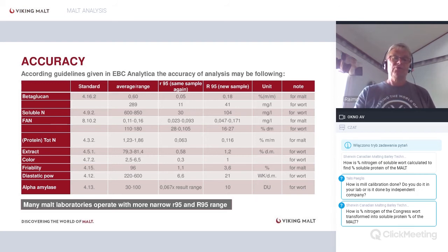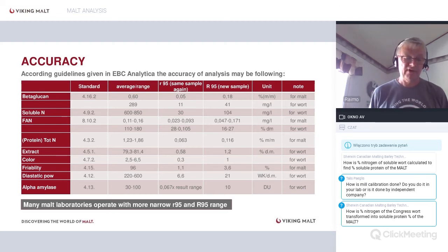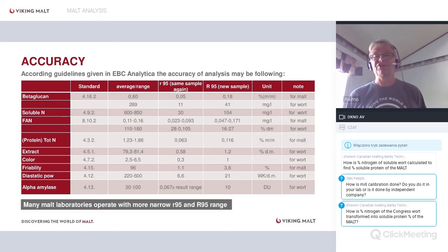So here you can see also the other numbers. Color measurement is actually quite sharp. The difference sometimes, if the laborant somebody checks some color hue a little bit darker than the other, may be the variation. The spectrophotometer checks the same all the time, but still you typically have a little bit higher color from the spectrophotometer than with the comparator.